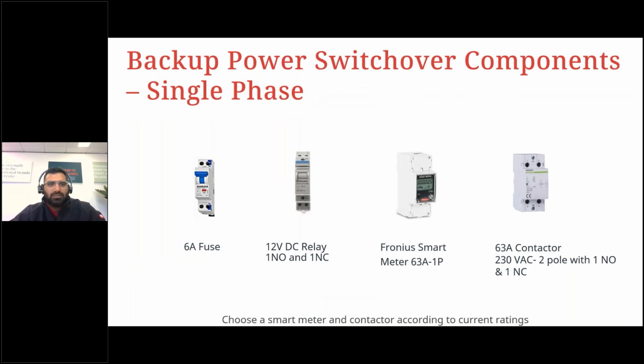All right, backup switchover components. So what do we need to run a system in backup when it comes to single phase backup supply? We have here a fuse, a relay, a smart meter, and a contactor. One thing you can notice here is the relay and the contactor both need to have a normally open and normally closed connection. Of course, we are using a smart meter 63 amps here as an example, but please make sure you use the right models depending on the current ratings that you are trying to control.